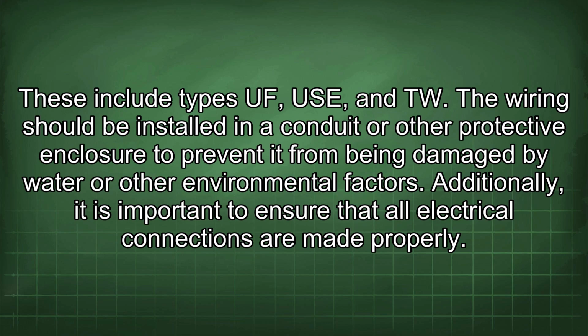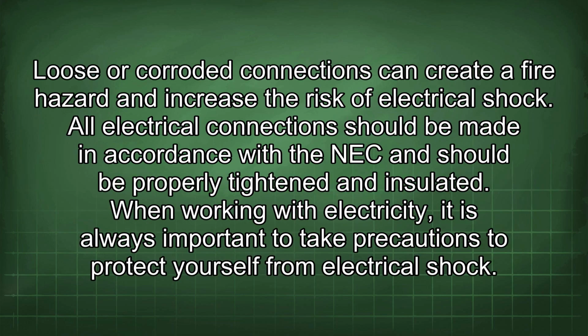or other environmental factors. Additionally, it is important to ensure that all electrical connections are made properly. Loose or corroded connections can create a fire hazard and increase the risk of electrical shock. All electrical connections should be made in accordance with the NEC and should be properly tightened and insulated.